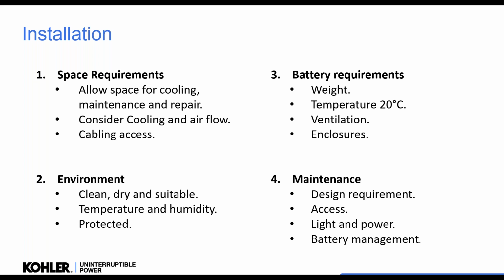We have to keep them at 20 degrees for longevity and for performance, because you will not get the autonomy if it's at 5 degrees. Okay, you won't get the time. There needs to be a small amount of ventilation to make sure we don't get hydrogen buildup, in the right type of enclosure to make it safe in the building. We must design for maintenance, okay, to allow access, light and power, and battery management.